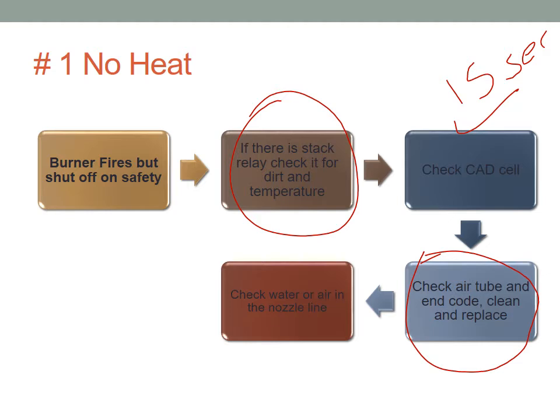And then check for water or air in the nozzle line. If the oil comes up, you have some flame, then it goes away. Sometimes there is not enough air, so we're functioning on the air and there's not enough oil. We're lighting the oil in the nozzle line, and as it goes out, it will stop. Then a little bit of oil will come in as the pressure increases, it comes out again, then it goes off. So make sure there's continuous oil flow and there is no water or air in the nozzle line.